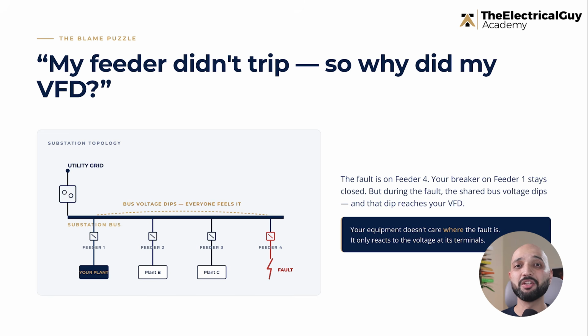This is why many site engineers get confused. They say, our feeder did not trip, then why did our VFD trip? And then the equipment manufacturer is blamed for that. But in reality, it may not be the manufacturer's fault, but the voltage sag due to a fault somewhere else in the system. The fault may be on a parallel feeder. It may be on the transmission system. It may be on the distribution network. It may be even inside a nearby large consumer's plant. And to be very honest, the equipment that you have connected in your system does not care where the fault happened. It only reacts to the voltage that reaches its terminal. If there is a problem there, it will trip.